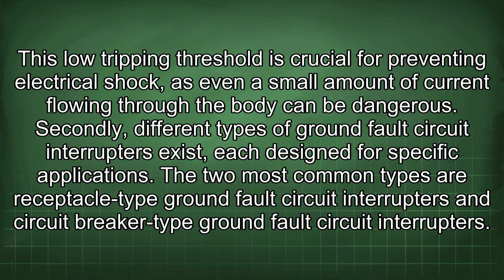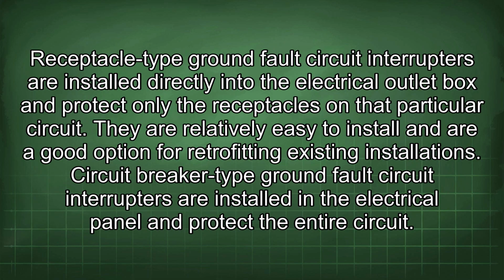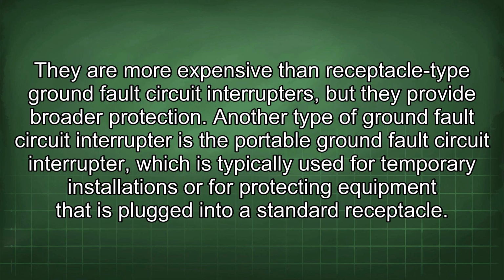The two most common types are receptacle type ground fault circuit interrupters and circuit breaker type ground fault circuit interrupters. Receptacle type ground fault circuit interrupters are installed directly into the electrical outlet box and protect only the receptacles on that particular circuit. They are relatively easy to install and are a good option for retrofitting existing installations. Circuit breaker type ground fault circuit interrupters are installed in the electrical panel and protect the entire circuit. They are more expensive than receptacle type ground fault circuit interrupters, but they provide broader protection.